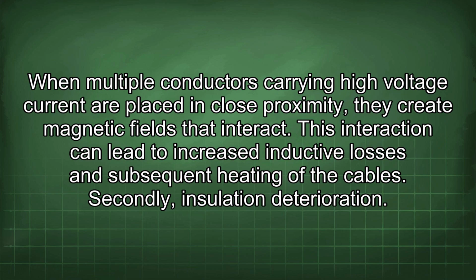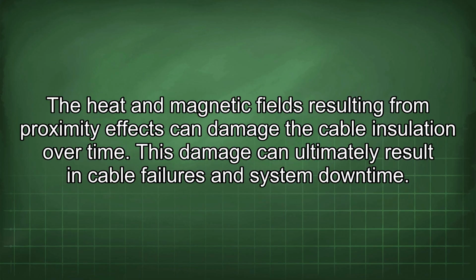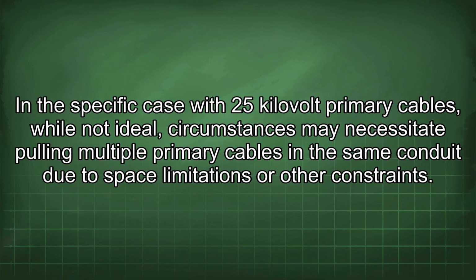Secondly, insulation deterioration. The heat and magnetic fields resulting from proximity effects can damage the cable insulation over time. This damage can ultimately result in cable failures and system downtime. In this specific case with 25 kV primary cables, while not ideal, circumstances may necessitate pulling multiple primary cables in the same conduit due to space limitations or other constraints.